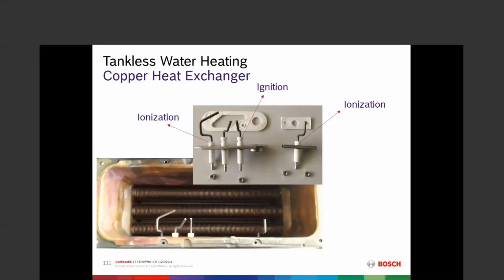2 electrode sets. The electrode sets are the same across the entire range of products. We have the primary electrode set, which includes the igniters. So we have 2 igniters that arc across each other. They don't arc back to the burner or anything. They arc across the igniters. And then we have our flame sensor for segment 1 and segment 2. Over on the right-hand side, we have our flame sensor for segment 3, and these flame sensors are in series.